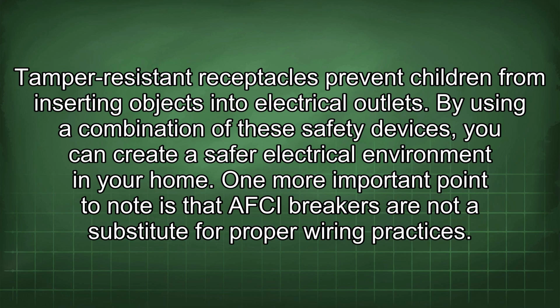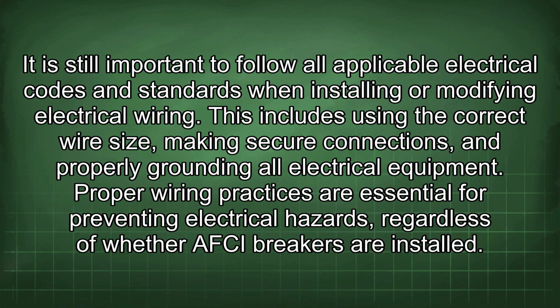One more important point to note is that AFCI breakers are not a substitute for proper wiring practices. It is still important to follow all applicable electrical codes and standards when installing or modifying electrical wiring. This includes using the correct wire size, making secure connections, and properly grounding all electrical equipment. Proper wiring practices are essential for preventing electrical hazards regardless of whether AFCI breakers are installed.